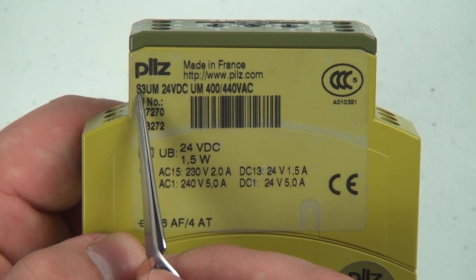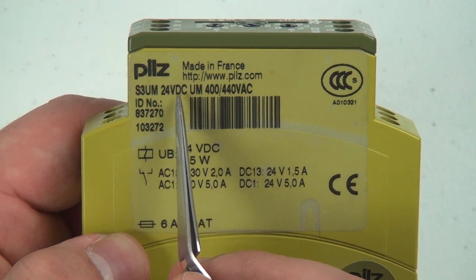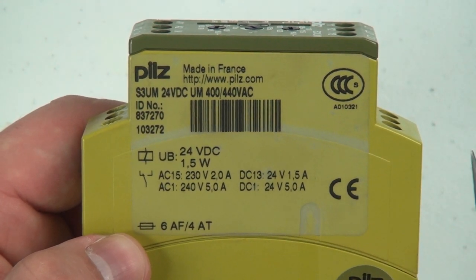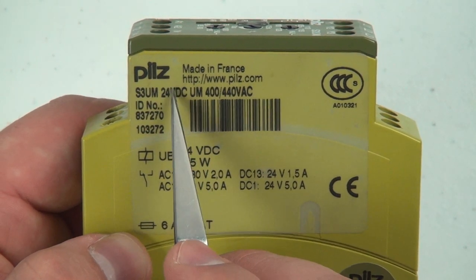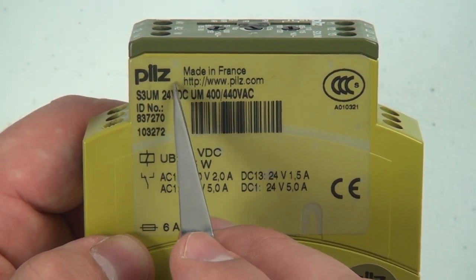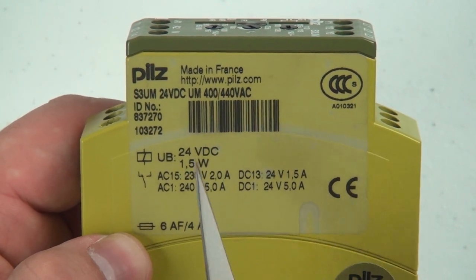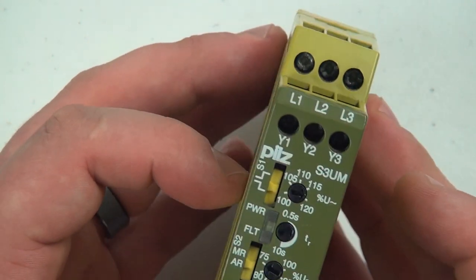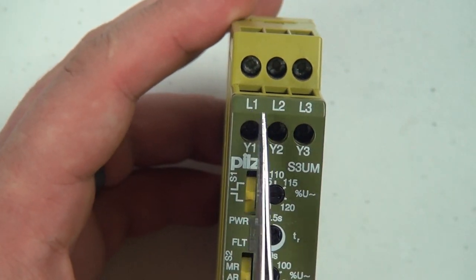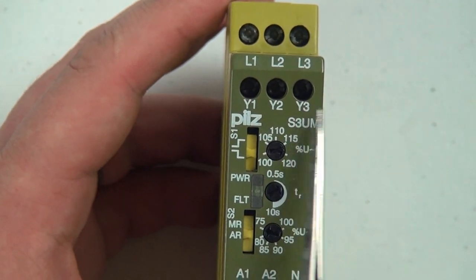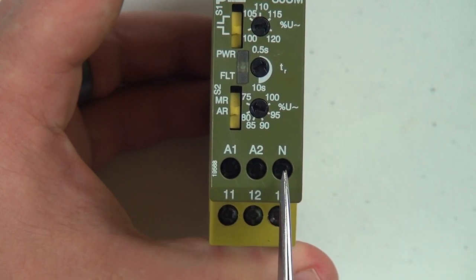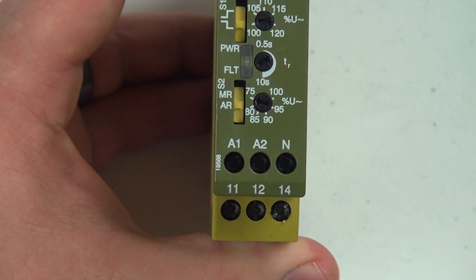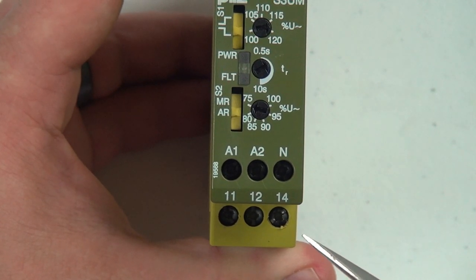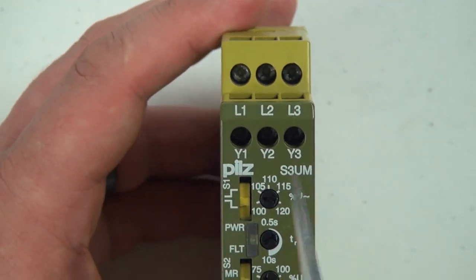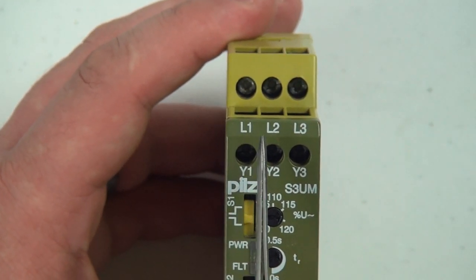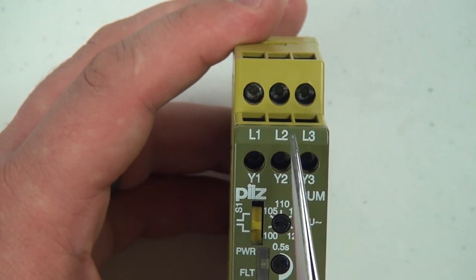This relay is the S3UM, and it is powered by 24 volts DC. And so let's go over that for a little bit to get a better understanding of what these two actually mean. On the front of the relay here, you will see L1, L2, L3, Y1, Y2, Y3, A1, A2, N, 11, 12, 14. What does that mean? So, as I mentioned previously, L1, L2, L3 are your three phases that are coming in.